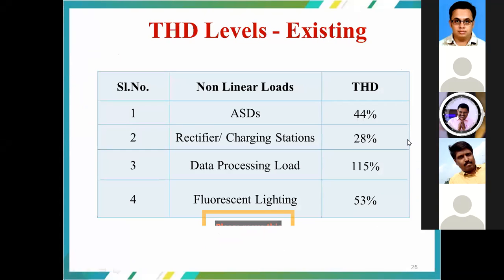And the THD levels, that is the total harmonic distortion levels of the existing converters, are as listed. For adjustable speed drives it is 44%, the rectifier or charging stations 28%, the data processing load, that is the SMPS or the UPS, 115%, and the fluorescent light fittings are capable of emitting 53% total harmonic distortion. As far as the IEEE standards are concerned, both voltage and current THD levels should be less than 5%. So imagine the problem raised because of these THD levels of the various converters.